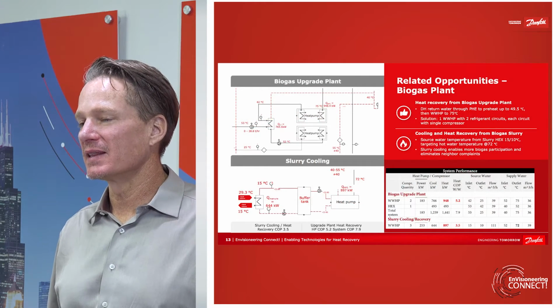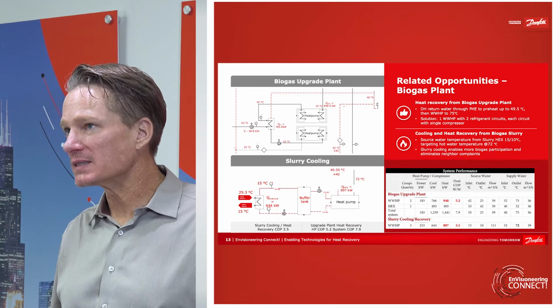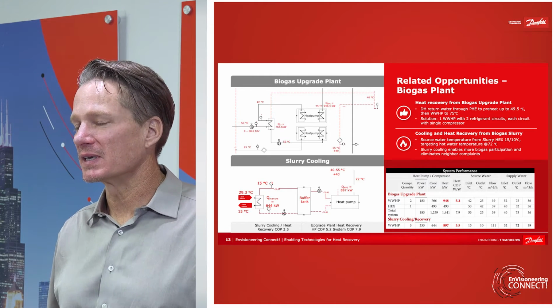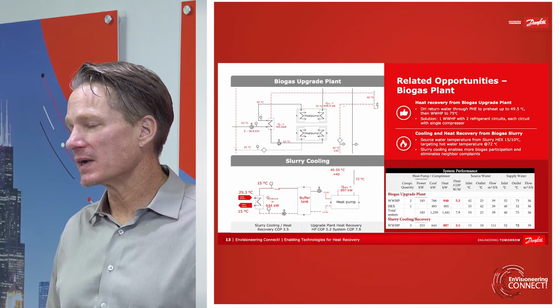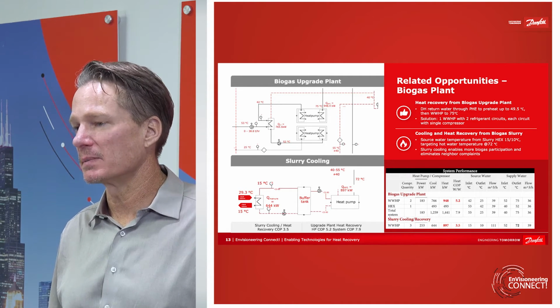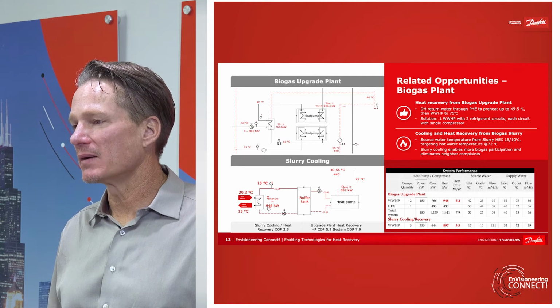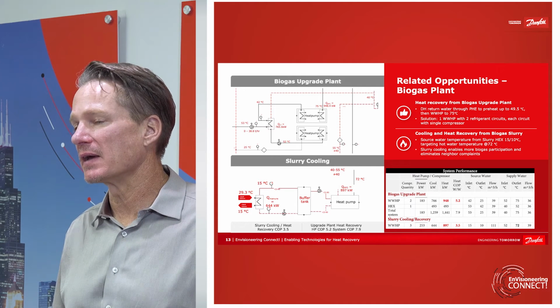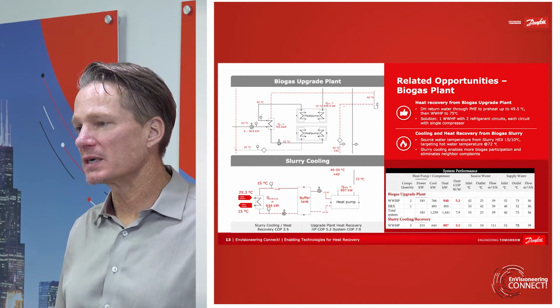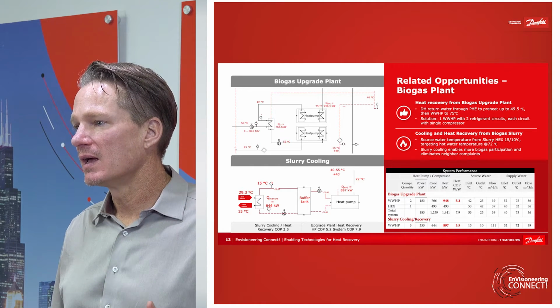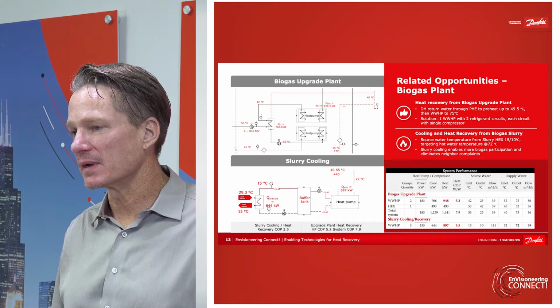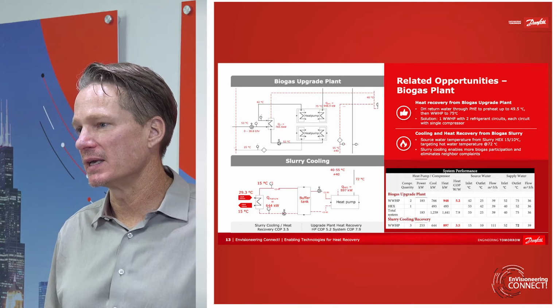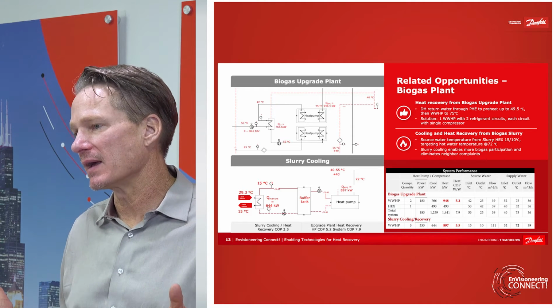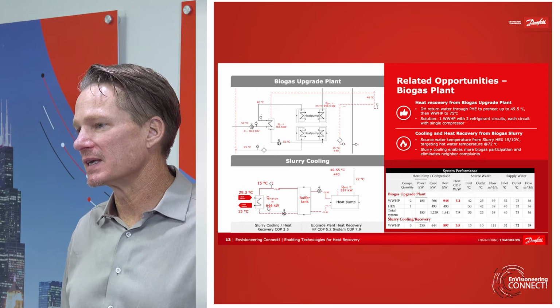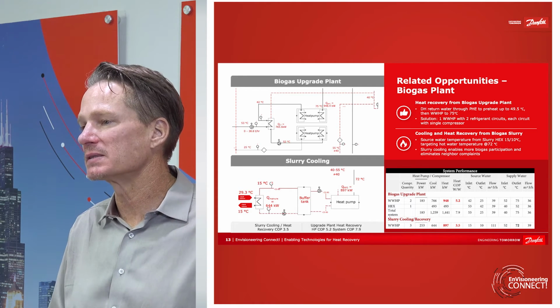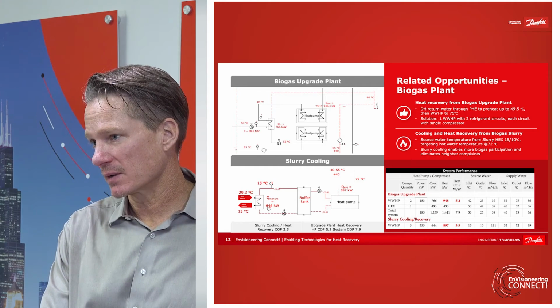Now, another related opportunity that we've been working on, and this is related in proximity based on its closeness to our Danfoss headquarters there in Nordborg. But we're also working on several similar opportunities in the rest of Denmark. But it's on biogas facilities. So you also have to decarbonize the natural gas grid, and how you do that is with biogas. And the production process of that biogas creates several different heat recovery opportunities. One of them is cooling the slurry to recover the heat to the district heating system, and then also on the upgrade plant where you're separating out the methane and the CO2. Both of those present heat recovery opportunities that we're showing what's possible also at these other facilities around Denmark.